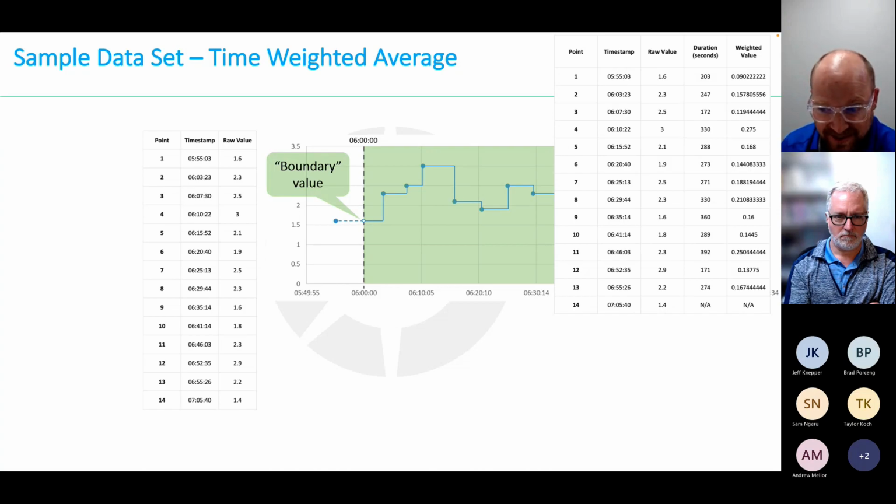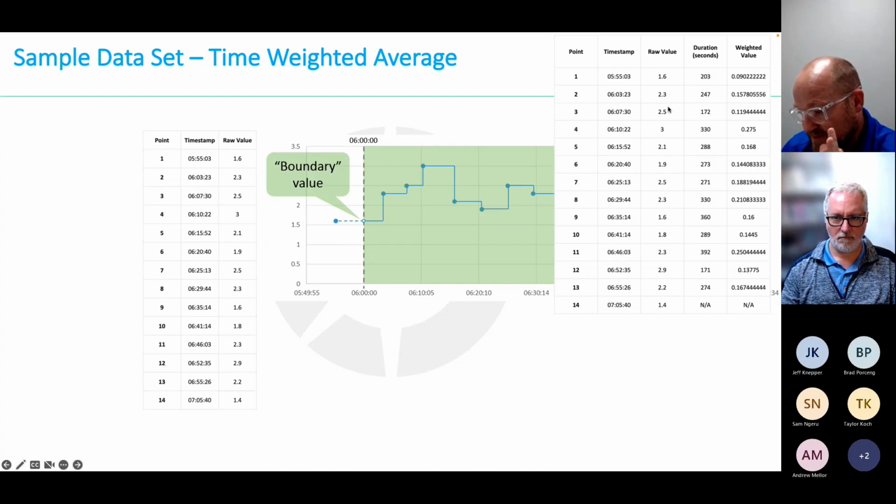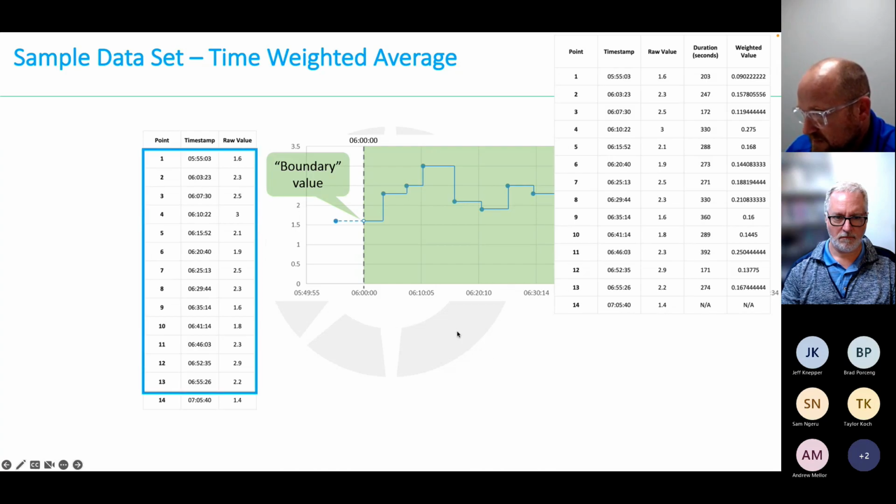It's just a matter of where the integral is getting computed, either here or on the instrumentation layer. So just be wary of that. One thing to be wary of with time-weighted averages, especially in flow transmitters or anything that records weights or totals, is if the value goes negative. If the instrument is not calibrated correctly, you might get negatives here, and negatives will subtract from the total. It looks like you add product back into the process. So just be careful to handle negative values as well. So we'll take all of that.